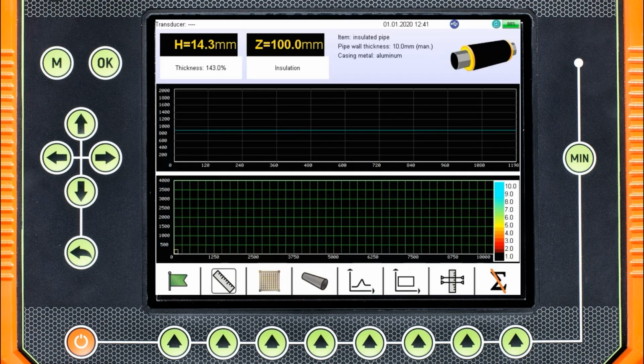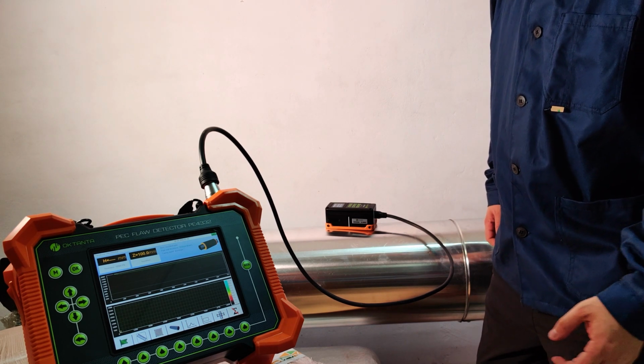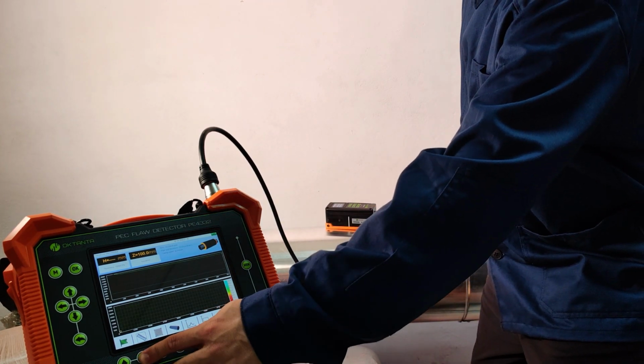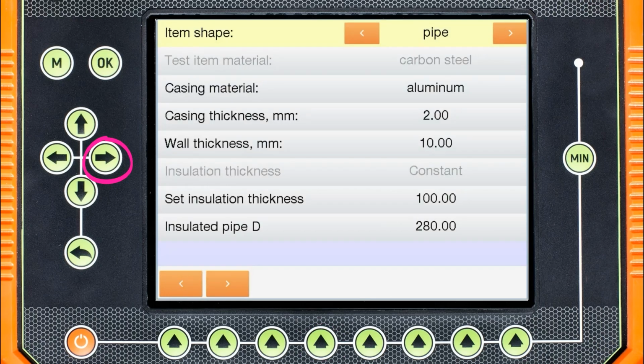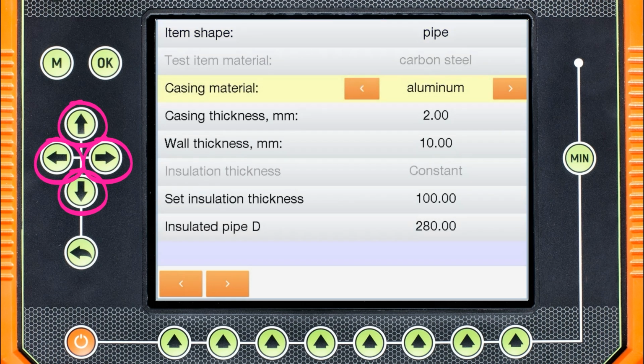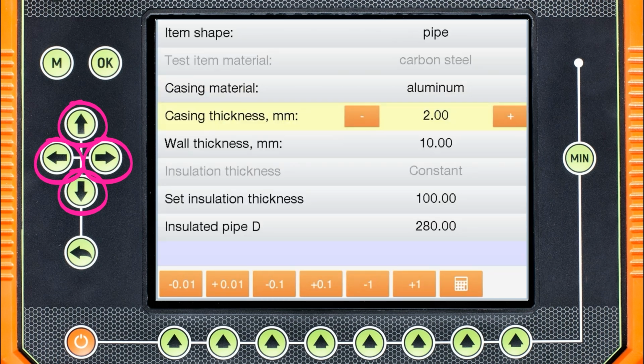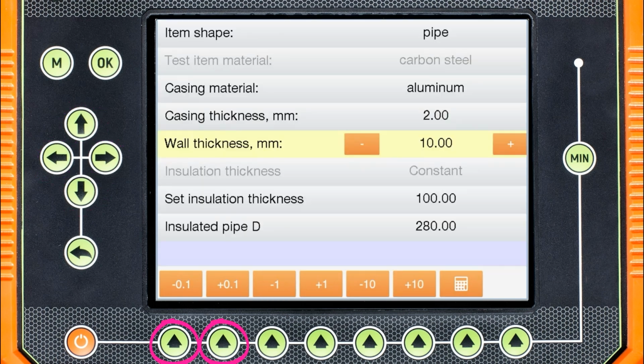Now, we will calibrate immediately on the measured item. Go to the menu of the test object parameters and set the item we want to measure. The shape of the test object, pipe or sheet. The material and thickness of the casing, if any. The nominal wall thickness at the point of calibration. The insulation thickness and insulated pipe diameter.